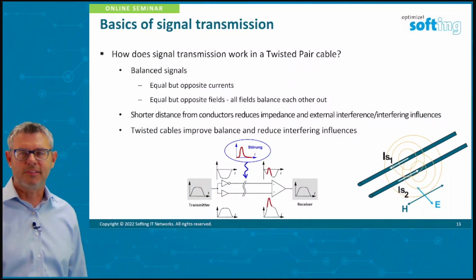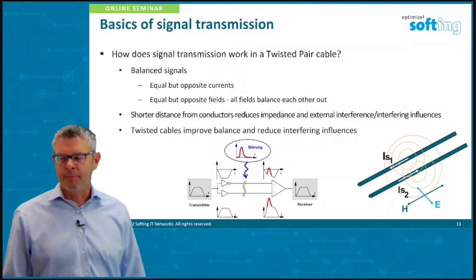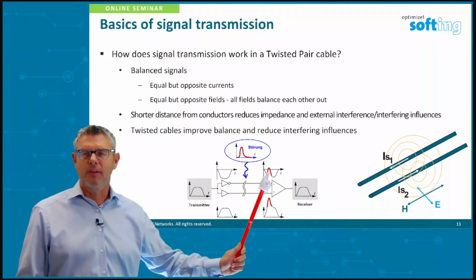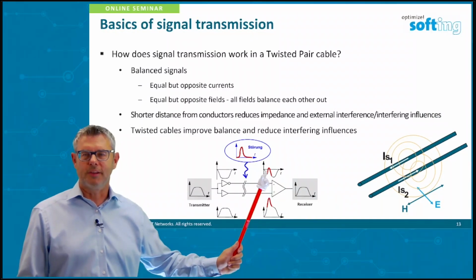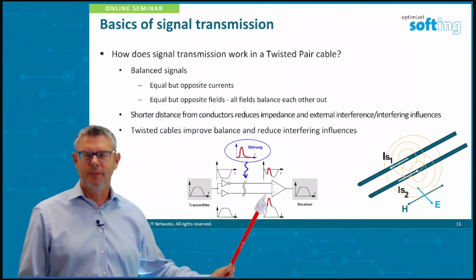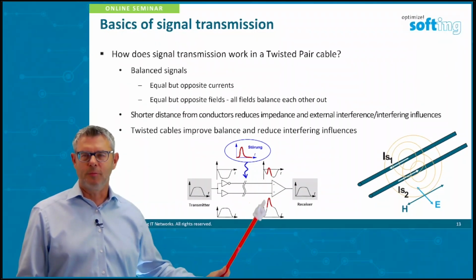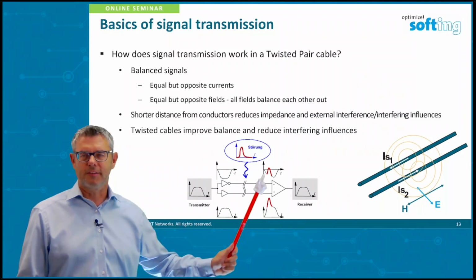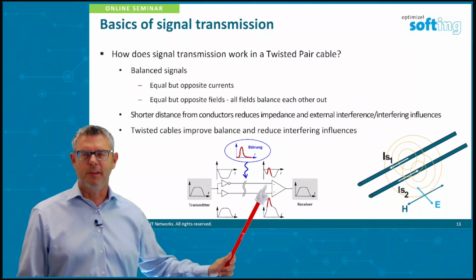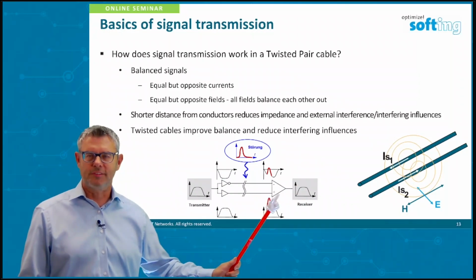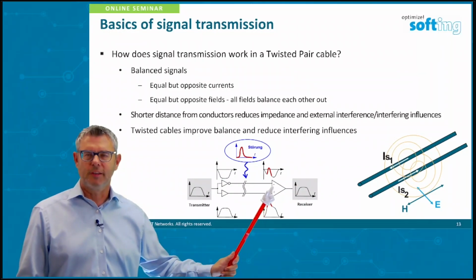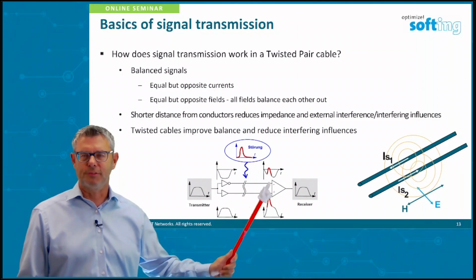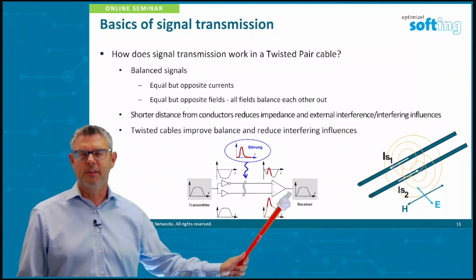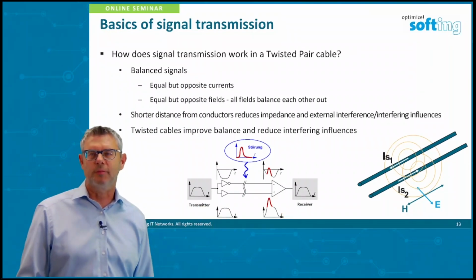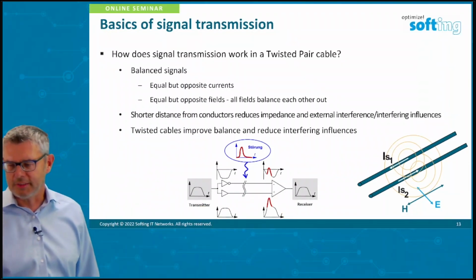If it ends up on our signals, they will look like this: a spike built into the waveform, here on top of the waveform. It went into both signals, with the same amplitude and direction. Now if this signal runs through the differential amplifier, the interference eliminates itself, and at the end we still receive the signal we transmitted from the beginning. That's the big advantage of balanced transmission of signals.